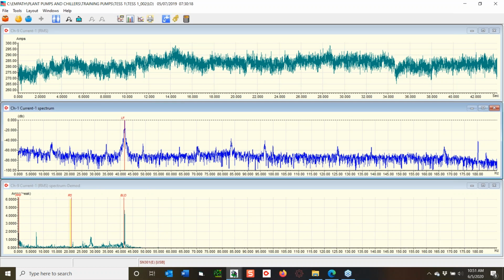Most medium voltage or high voltage drives don't have CT-PT secondary. Can we do this test? I usually at that point will use just the current clamps. So I can still do this. I'll lose torque and I lose kilowatts, but I can still do current signature analysis off of one phase if I needed to.